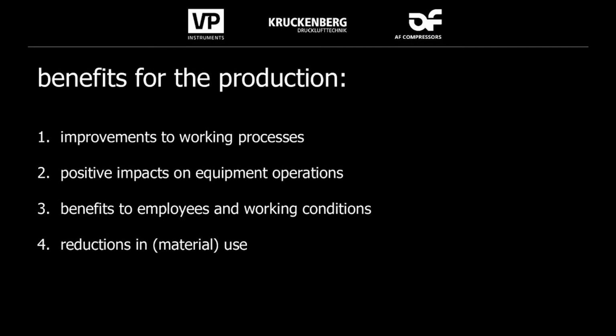And when they started this kind of pressing process, they had a 40-second cycle to produce their product. But nowadays, they are facing a 100-second cycle. With the repair of the leakages and the indicating of the problem, they could optimize the process back to a 40-second cycle, which was enabling the client to produce around 1,400 euros per day more product value output. And this production line was running 360 days per year, which is a huge saving. And this was opening many doors for us. Of course, they realized with this single case, we maybe should listen. But you have to prove it.